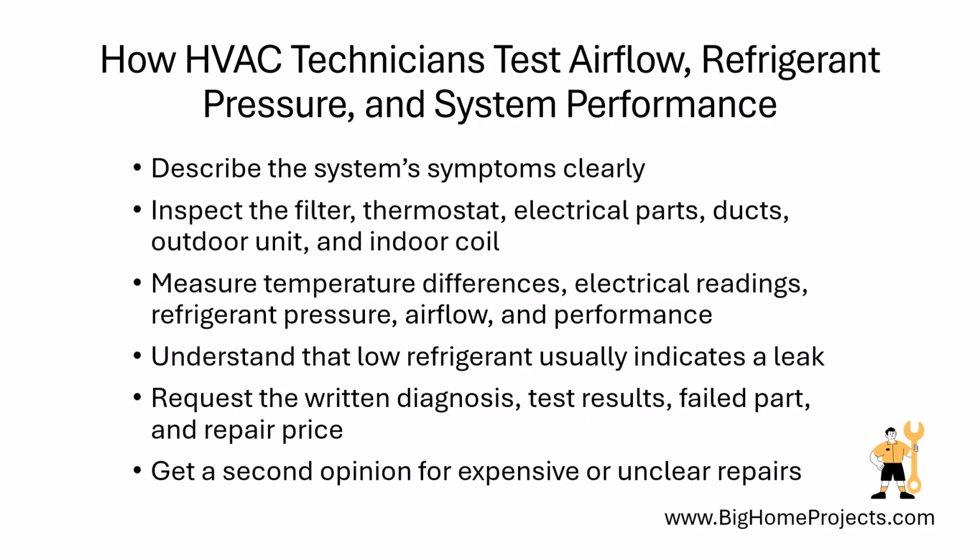An accurate diagnosis begins with a clear description of what your system is doing, such as weak airflow, unusual noises, or rooms that stay too warm. The technician should inspect the filter, thermostat, electrical parts, ductwork, outdoor unit, and indoor coil instead of guessing from one symptom. They may measure supply and return air temperatures, electrical readings, refrigerant pressure, airflow, and system performance. Ask the technician to explain what each measurement means and what normal readings should look like.